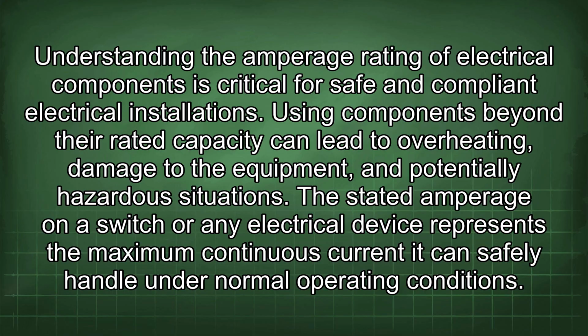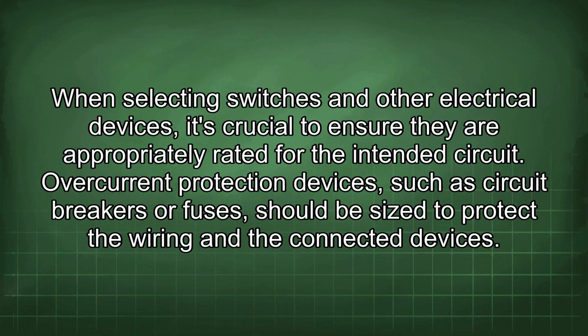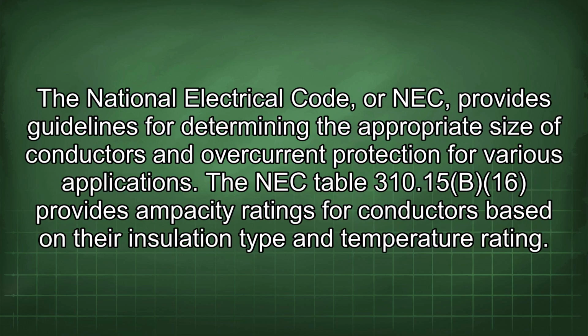The stated amperage on a switch or any electrical device represents the maximum continuous current it can safely handle under normal operating conditions. When selecting switches and other electrical devices, it's crucial to ensure they are appropriately rated for the intended circuit. Overcurrent protection devices, such as circuit breakers or fuses, should be sized to protect the wiring and the connected devices. The National Electrical Code, or NEC, provides guidelines for determining the appropriate size of conductors and overcurrent protection for various applications.